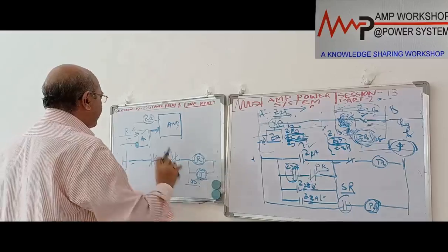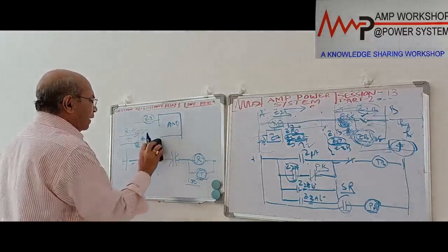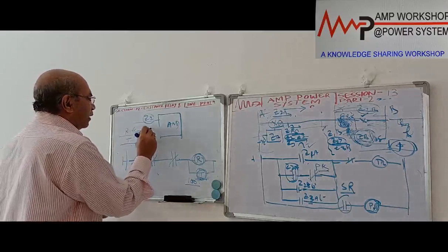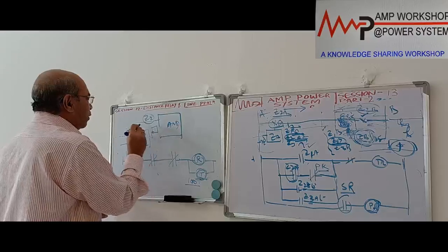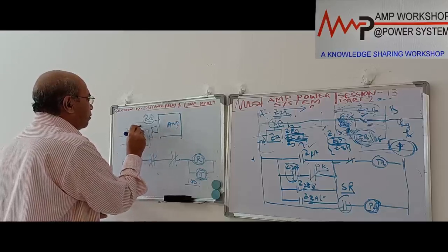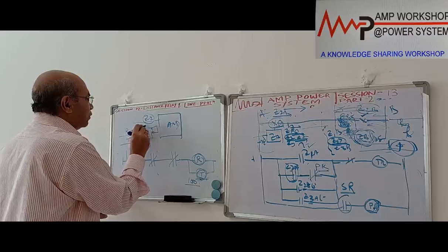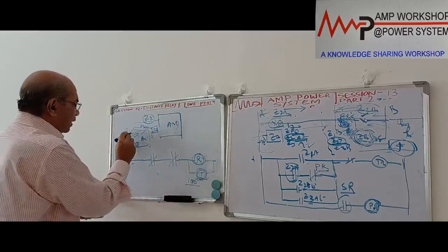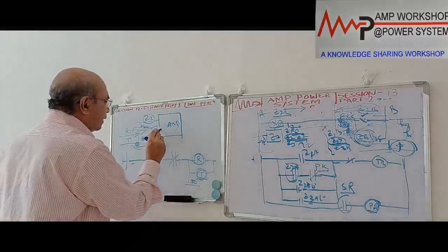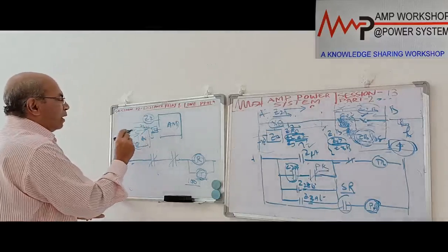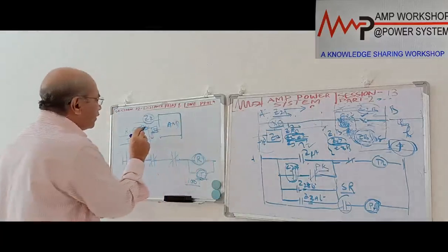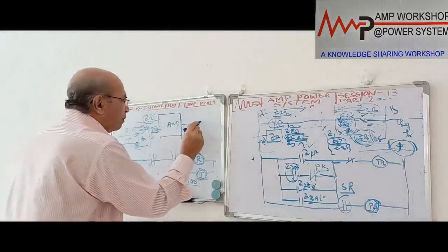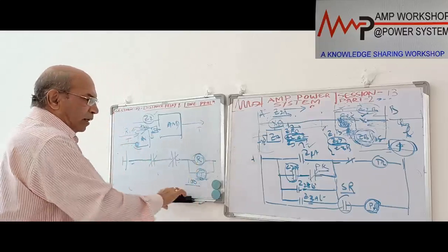Here is an AND gate, and here is another option. If the signal is received, another gate will come here. This is Z1 signal receive, Z2 signal receive. This is your OR gate. So when these two are high, it can be high, or if the Z1 signal from the other end is received, in that case it is also high. And if Z2 has operated, then it will give the trip command. So that is the case here.